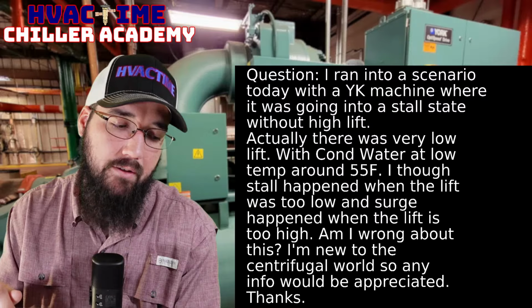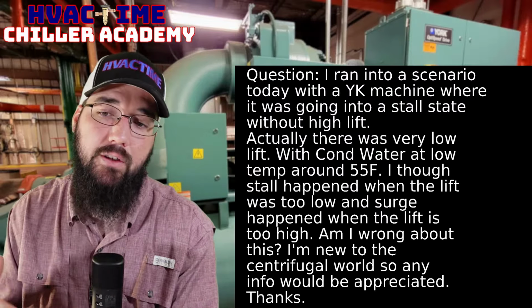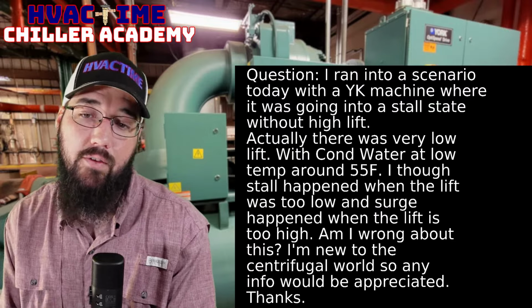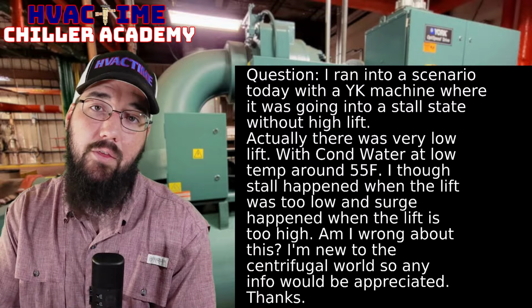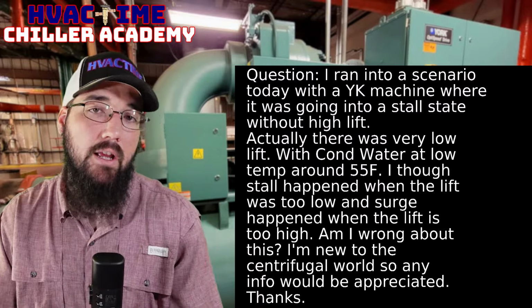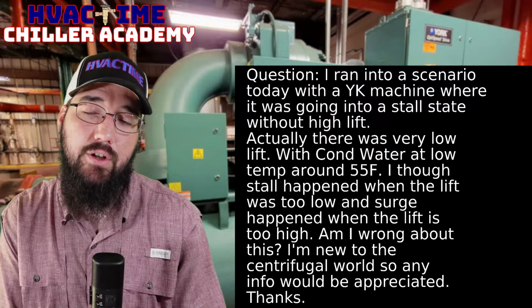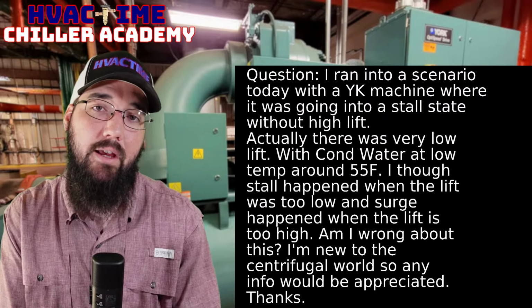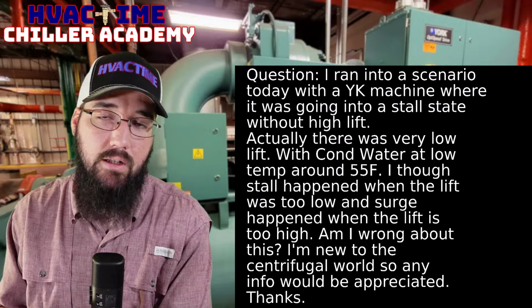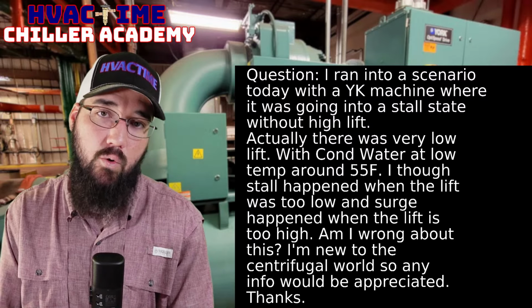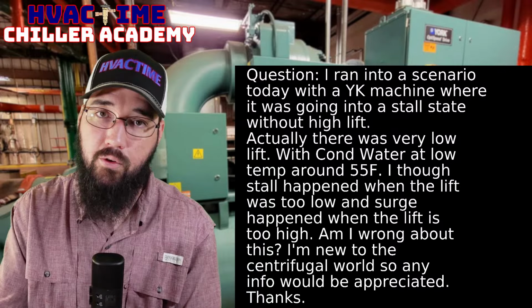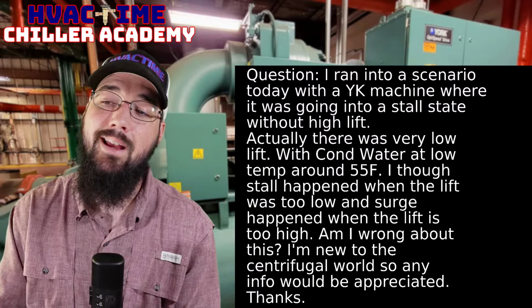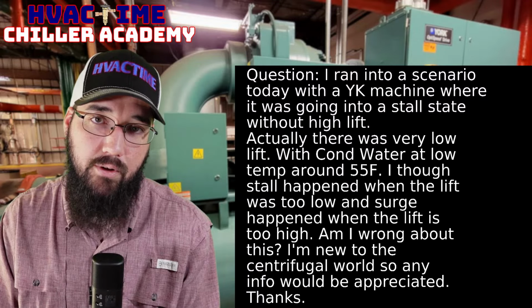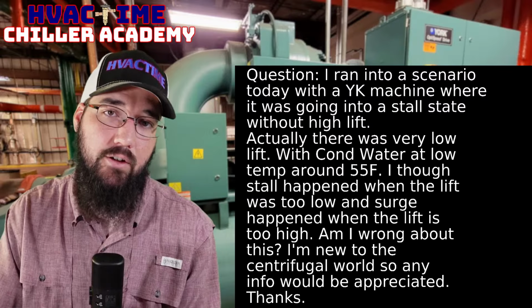And then there are going to be scenarios where you'll see that the IGVs only go open so far, and then we increase speed and then we open the IGVs more. Again, that plays back into that graph. The machine knows to do its best to stay out of a surge, and so it's going to step these things accordingly. In a perfect world, you go full IGV 100% open, and then we start increasing the compressor speed. But that's only if conditions allow.